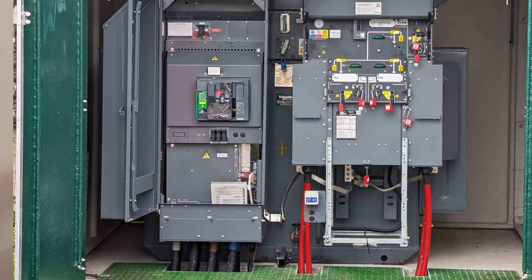In simple terms, transformers are just two coils of wire, one inside the other, each having a different number of turns. So maybe one transformer has coil one with a hundred turns and coil two with a thousand. If you put electricity into one, when it comes out of the other it is either ten times higher or ten times lower voltage, depending on which coil you put it into first. So now we're down to just 11,000 volts, at 50 hertz — meaning it alternates back and forth 50 times a second — and that passes through a transformer that reduces it to 450 volts 50 hertz.